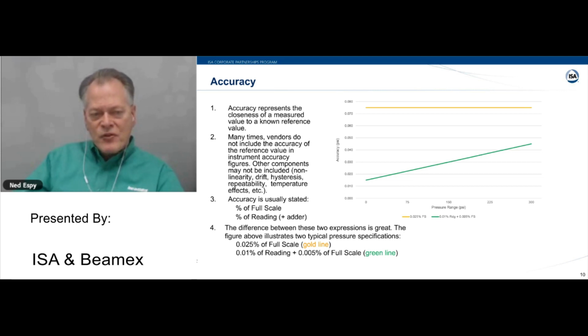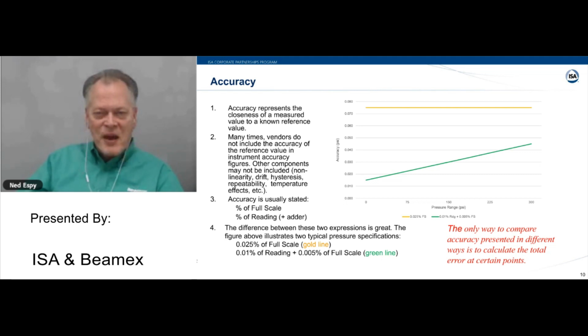So here's the graph. If you look at the full scale statement, it's this gold line up here, and this is 0.025%. If you have a statement that says it's 0.01% of reading and then a percent of full scale, like a compound statement, here's that base error, that 0.005% of full scale, and then here's the percent of reading piece going uphill on this slope. So in this example, this is significantly more accurate than this statement, but when you're doing this type of analysis, the only way you can compare different statements and specifications and all the fine print is to calculate exact error at particular points for what you're interested in measuring.